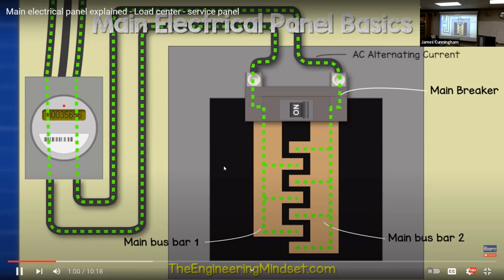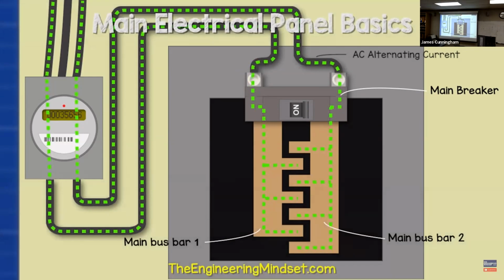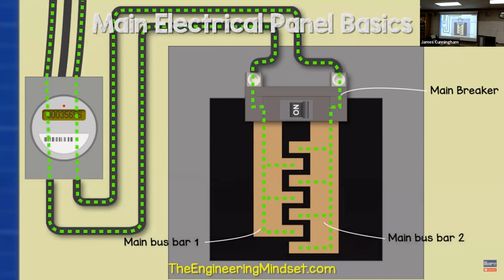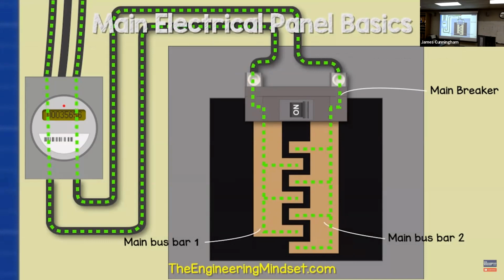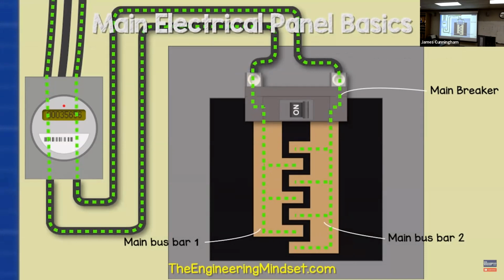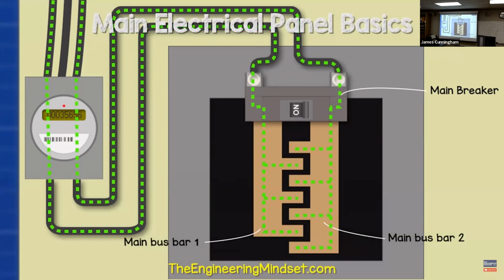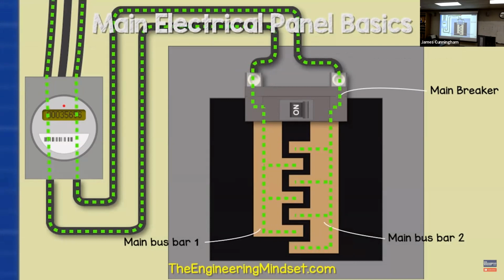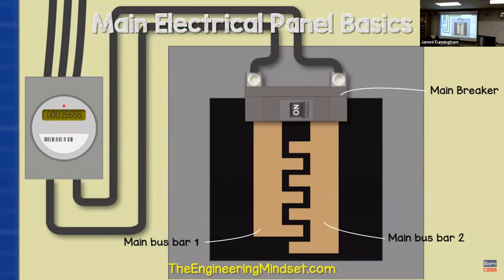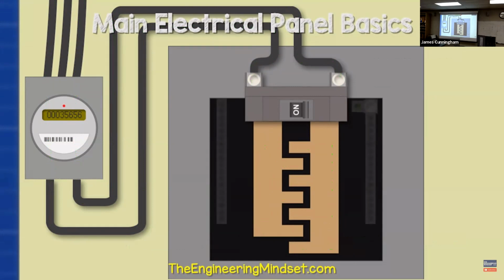AC or alternating current. These bus bars, as well as the lugs, are not insulated, they are live or hot. The main breaker can be manually flipped to cut the power to everything downstream of the main breaker. The main breaker will also provide overcurrent protection to the property. It is rated to handle a certain amount of electrical current passing through it, typically between 100 and 200 amps. If this value is exceeded, then it will trip automatically to try and protect the property and its electrical circuits.